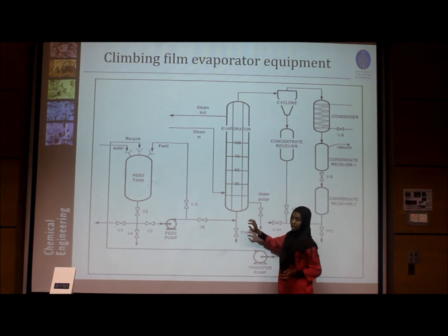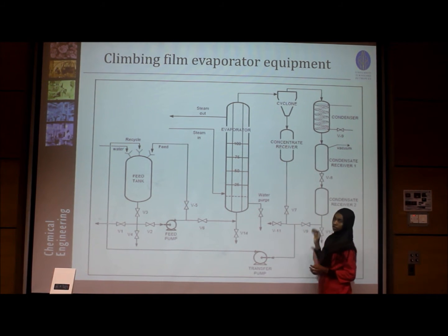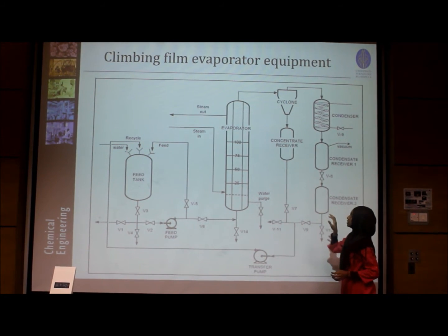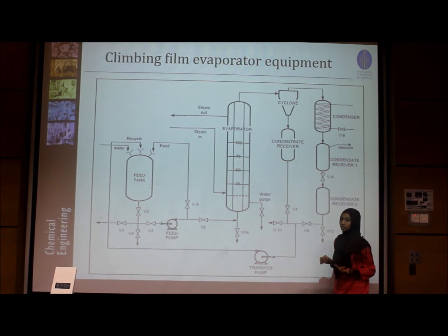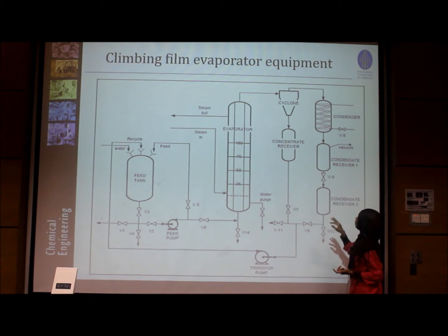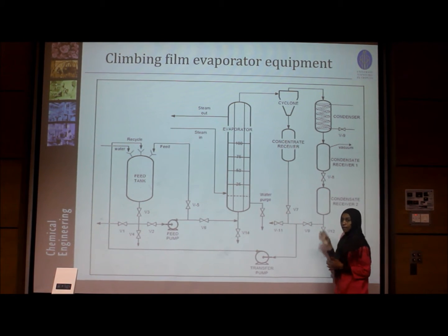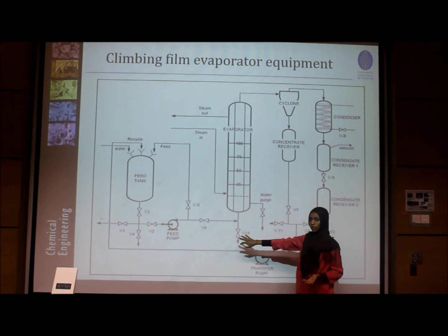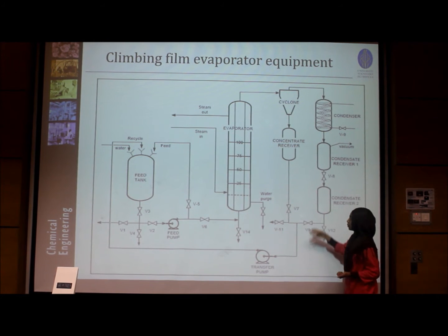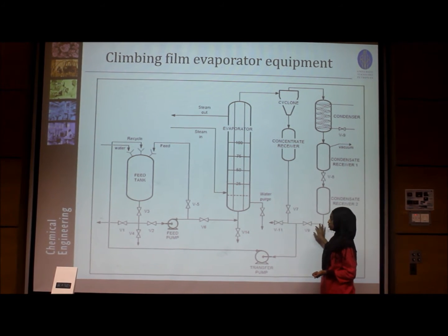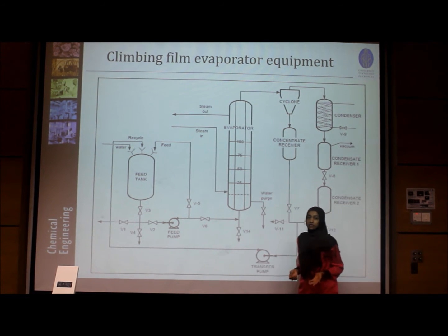With this high velocity, the mixture goes to the top of the evaporator and is discharged into the separator, where it is separated into vapor and concentrated liquid. The vapor goes to the condenser where it is condensed and can be recycled for energy efficiency. The product can be taken out or recycled back into the feed tank for more concentration.